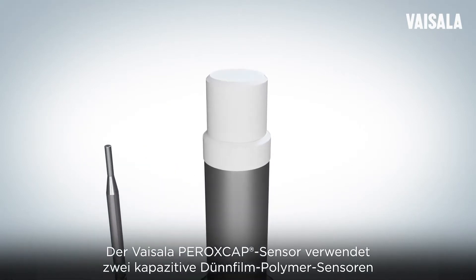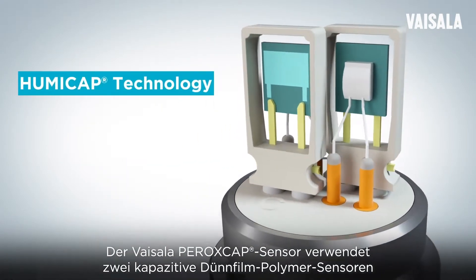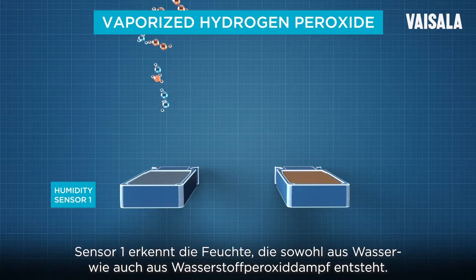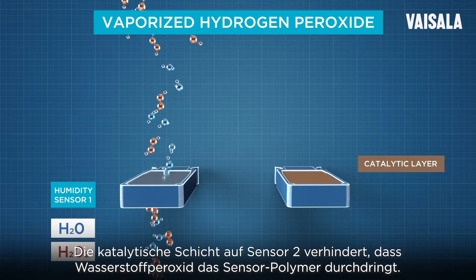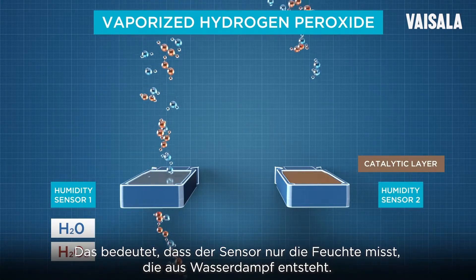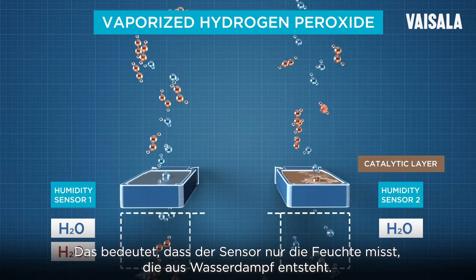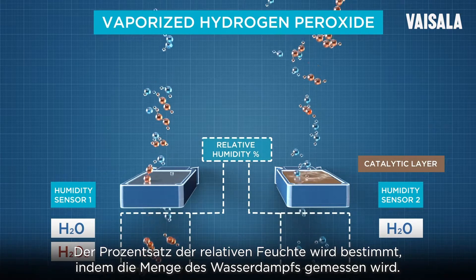The Vaisala PEROXCAP sensor uses two capacitive thin-film polymer sensors and is based on our proven reliable HUMICAP technology. Sensor 1 detects the humidity generated by both water and hydrogen peroxide vapor. The catalytic layer on top of sensor 2 prevents hydrogen peroxide from penetrating the sensing polymer, meaning that sensor 2 only measures the humidity generated by water vapor. The relative humidity percentage is determined by measuring the amount of water vapor.